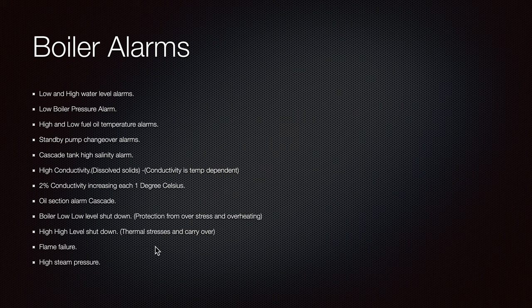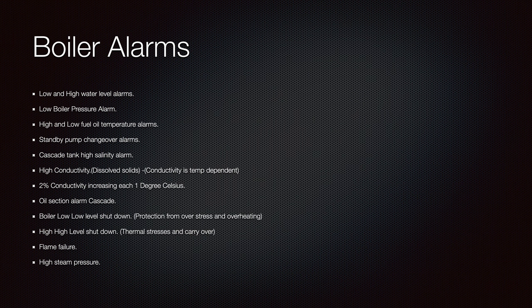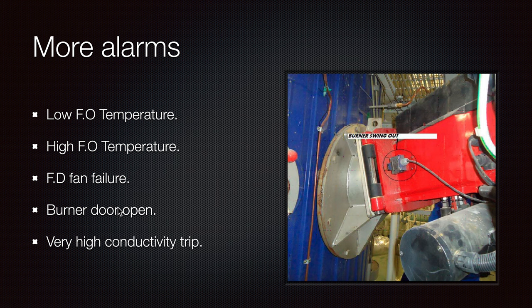Boiler alarms also include flame failure and high steam pressure. More alarms can be set in the system as precautionary measures, depending on what kind of boiler it is and the program: burner swing-out, low fuel oil temperature, high fuel oil temperature, force draft fan failure, burner door open, very high conductivity trip. Low fuel load temperature is for heavy fuel, and high fuel oil temperature is for diesel, which is also dangerous to burn due to its low flash point. We need to keep everything within the proper range.